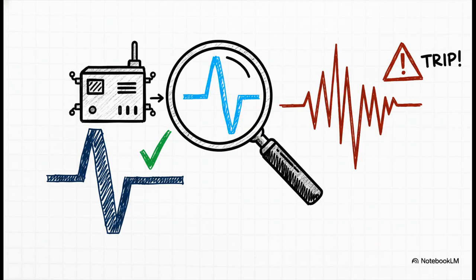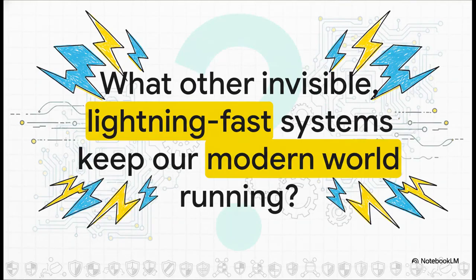But this is where the engineering gets so clever. Modern relays don't just measure the amount of current, their algorithms actually analyze the shape of the current's waveform. They're smart enough to recognize the distorted, messy signature of a saturated sensor versus the clear, unique signature of a true internal fault. Basically, they can see right through the blindness. So there you have it. Deep inside our electrical substations, these silent guardians are on watch, 24/7, balancing the flow of power. They operate in milliseconds, making these huge decisions that prevent catastrophic failures and keep our lights on. It really makes you wonder, what other invisible, lightning-fast systems are out there quietly keeping our whole world running?